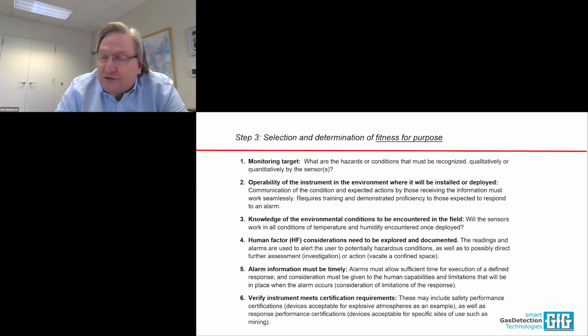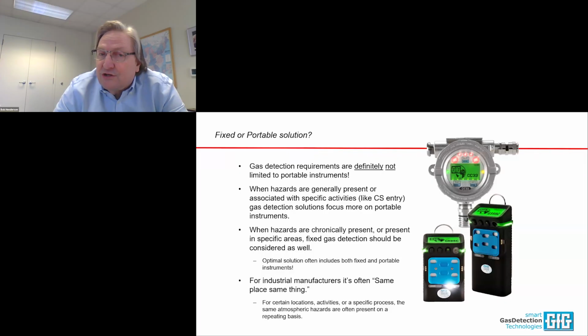But outside of confined space entry, especially just for general and fixed gas detection systems at a manufacturing site, it's hard to find a lot of good guidance. This white paper really provides that guidance. It helps you understand the monitoring target. Some of the concerns that you need to address are the operability of any instruments, be they portable or fixed, in the environment where they are installed or deployed. What are the environmental conditions and how might that affect your ability to use the equipment or for the equipment to be properly operable? Human factor considerations, alarm information, what you're going to do with that information, how you verify the instruments meet certification requirements that you might need to deal with at your site or for that process or procedure.